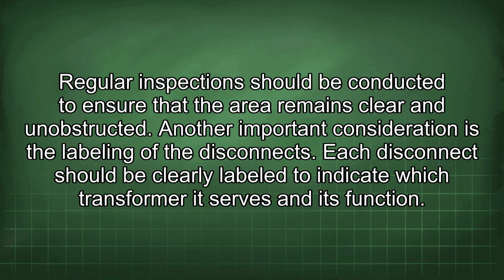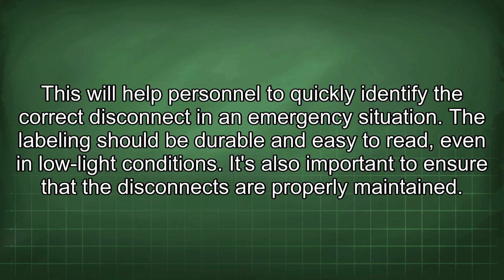Another important consideration is the labeling of the disconnects. Each disconnect should be clearly labeled to indicate which transformer it serves and its function. This will help personnel to quickly identify the correct disconnect in an emergency situation. The labeling should be durable and easy to read even in low light conditions.